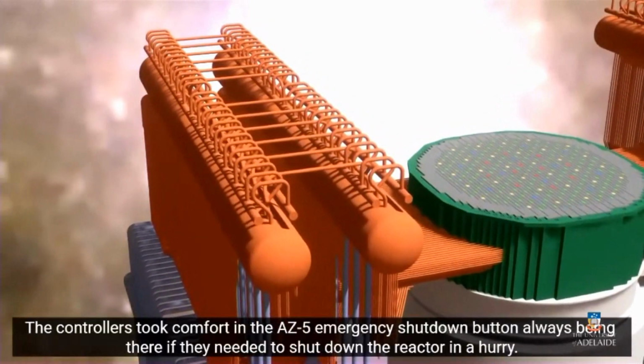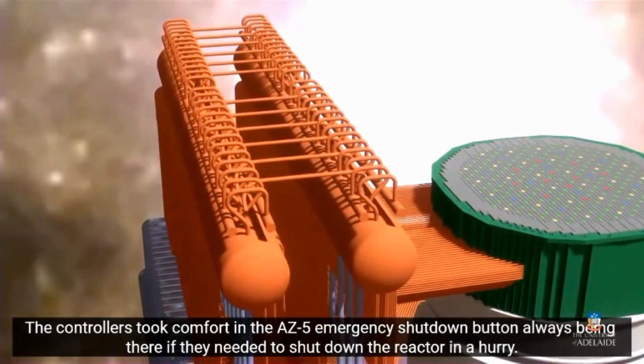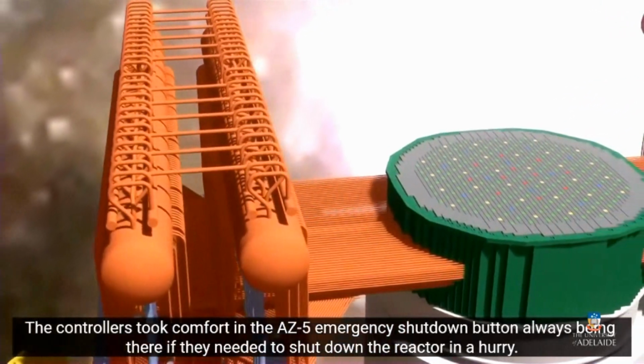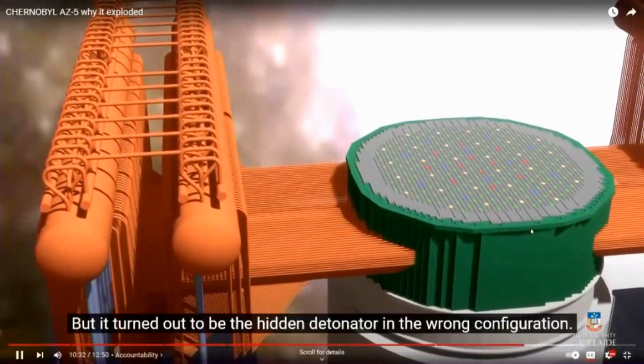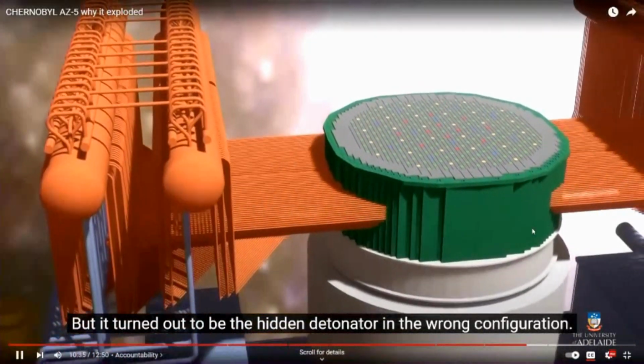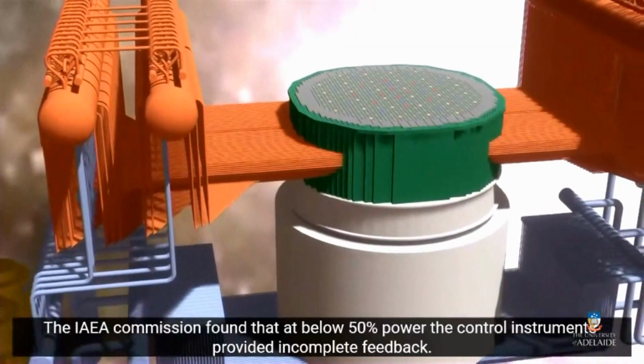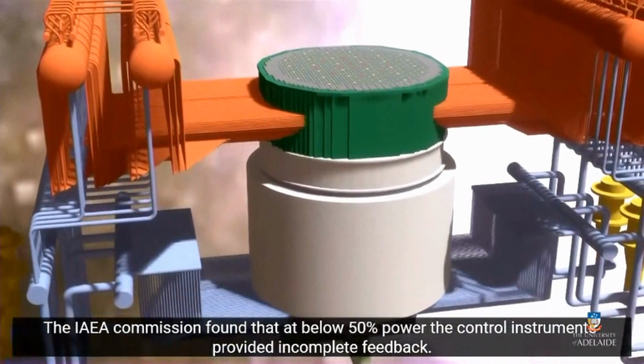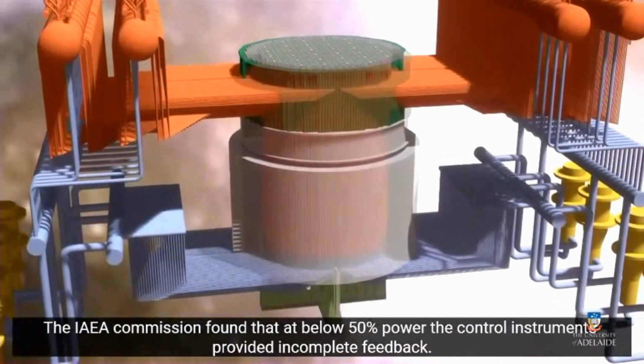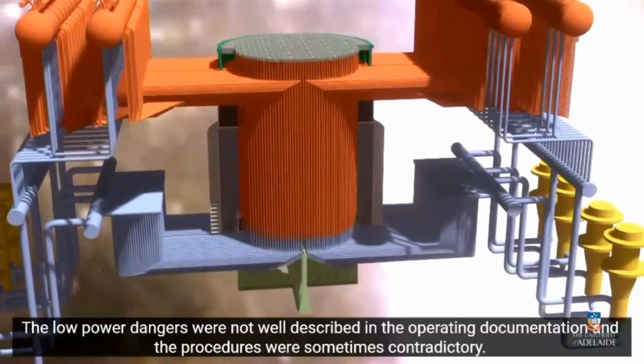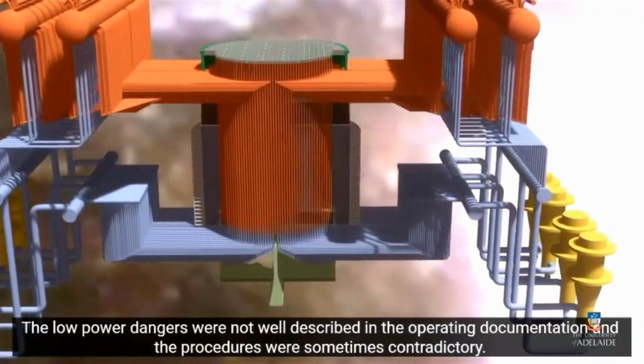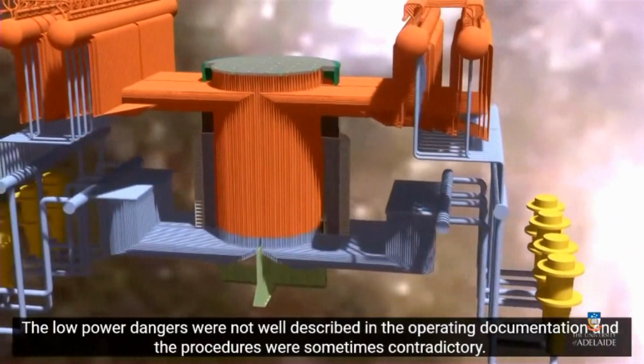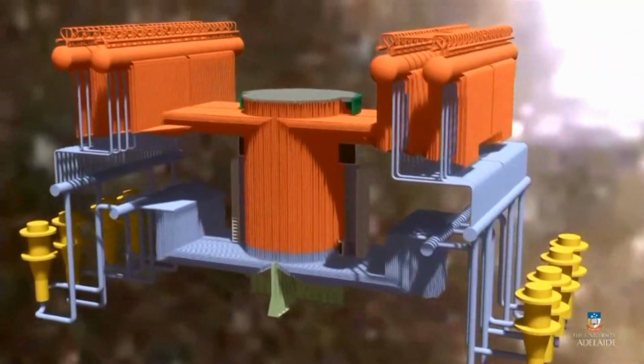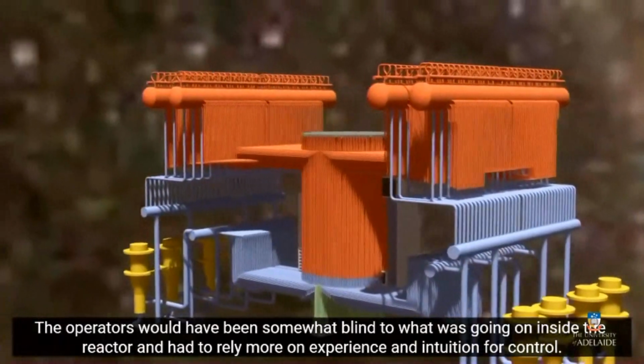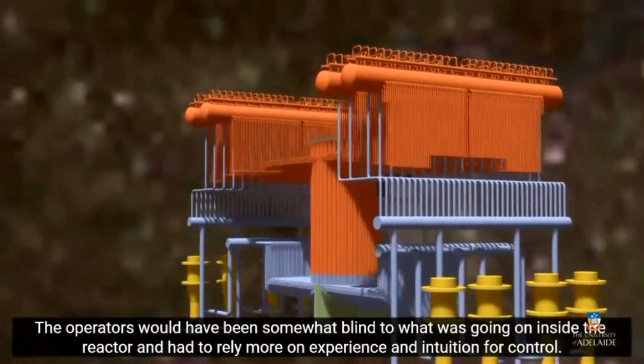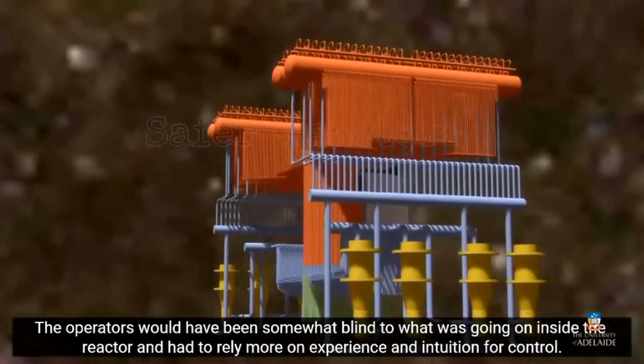The controllers took comfort in the AZ-5 emergency shutdown button always being there if they needed to shut down the reactor in a hurry. But it turned out to be the hidden detonator in the wrong configuration. The IAEA Commission states that at below 50% power, the control instruments provided incomplete feedback. The low power dangers were not well described in the operating documentation, and the procedures were sometimes contradictory. The operators would have been somewhat blind to what was going on inside the reactor, and had to rely more on experience and intuition for control.